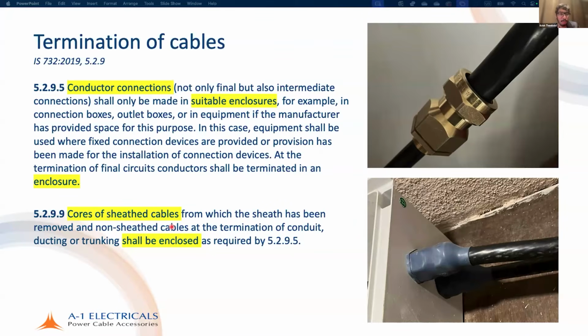There's a sheath that goes on top. The cores of sheathed cable from which the sheath has been removed, and non-sheath cable. So, for example, just single core cables, which are non-sheath, at the termination of conduit, ducting or trunking shall be enclosed as required by 5.2.9.5. So when a cable enters an enclosure, it has to be correctly enclosed.